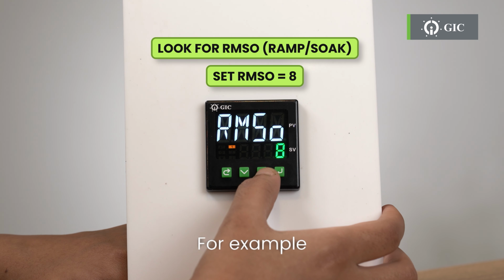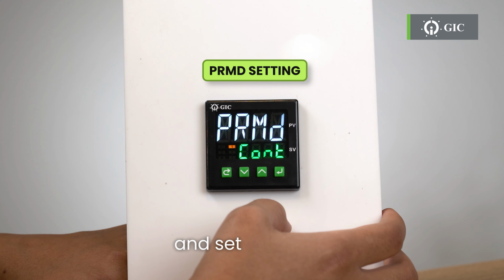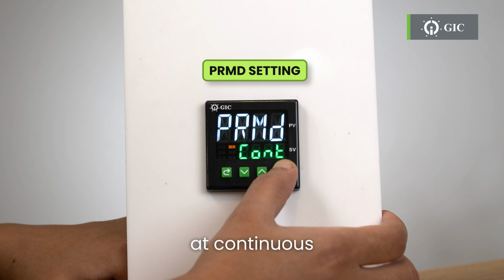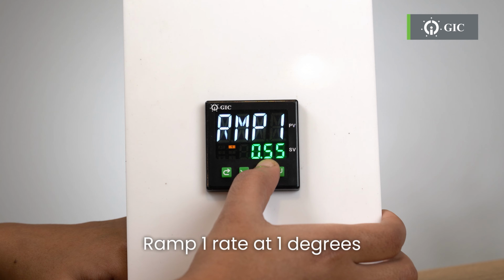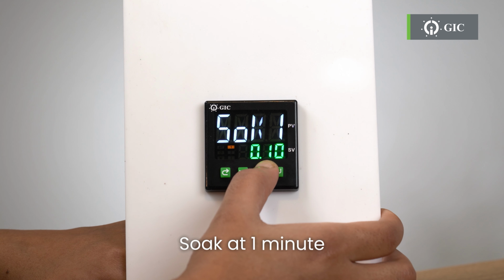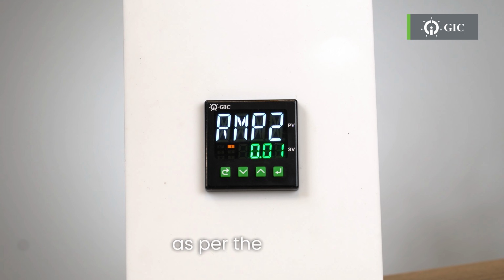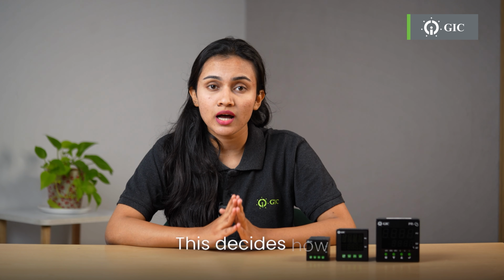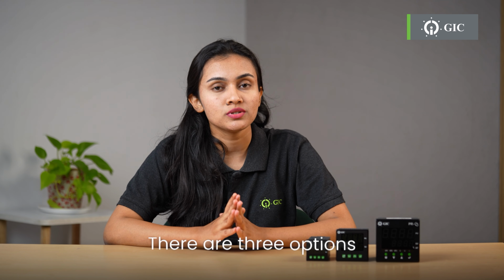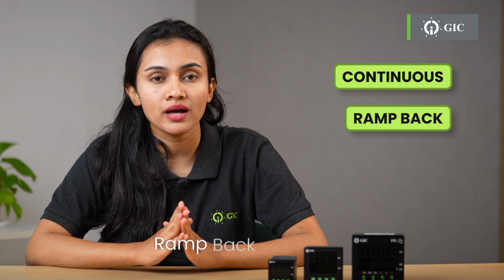For example, next enter the setting and set the PRMD at continuous, ramp 1 rate at 1 degree, soak at 1 minute. As per the system requirement, we can set the ramp rate and soak rate for the further ramps and soaks. This decides how the controller behaves if a power failure occurs. There are 3 options, that is continuous, ramp back, and reset.